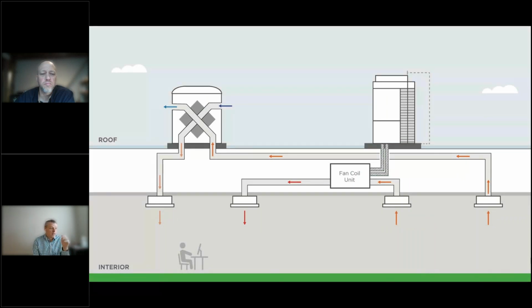The first thing we need with this system is that we fully decouple it—separating the ventilation air from the heating and cooling fan coil units. This approach allows the two systems to be controlled and optimized to provide the critical functions they're intended for, without crossing over, so the HVAC system isn't also providing ventilation, which can cause increased energy use. Now you can schedule the ventilation system to meet ventilation needs according to occupancy, so it's flexible, while the decoupled primary heating and cooling system delivers comfort conditions and controls temperature based on the zones.